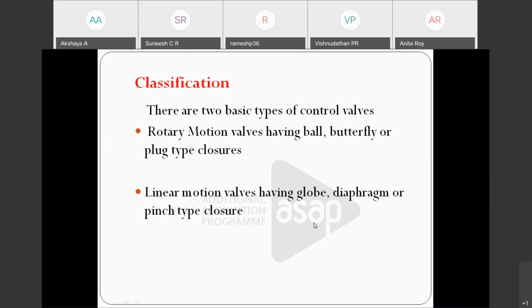Broadly, you are classifying the valves into two: one with linear motion and one that generates rotary motion. For linear motion, it can be either a globe type or a diaphragm type. You can see the stem moving. If it moves in one direction, the inlet will be open, and if it moves in the other direction, the inlet will be closed. The motion is actually a linear motion, which is why we call them linear valves.